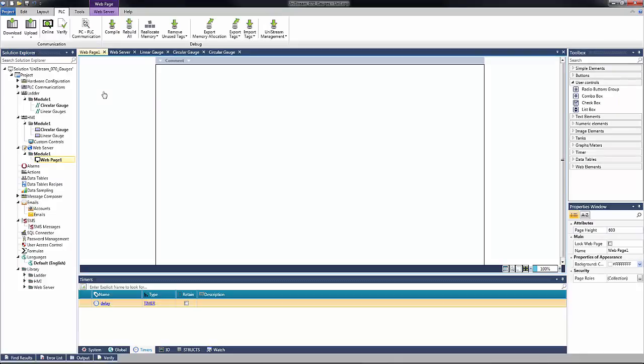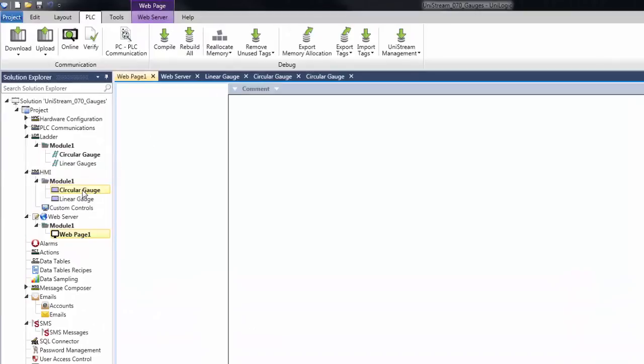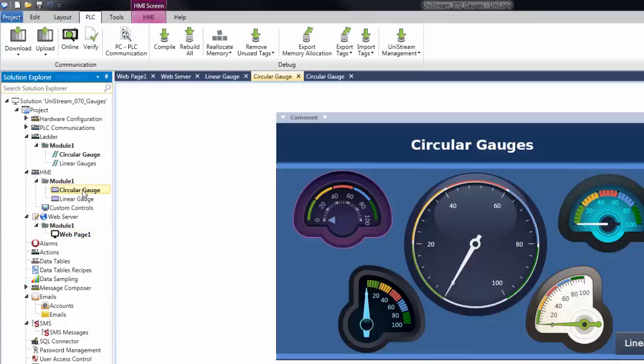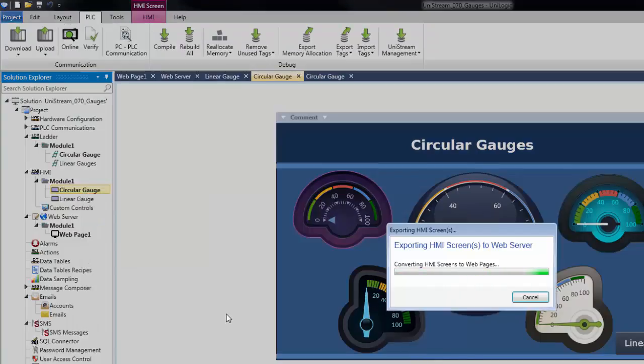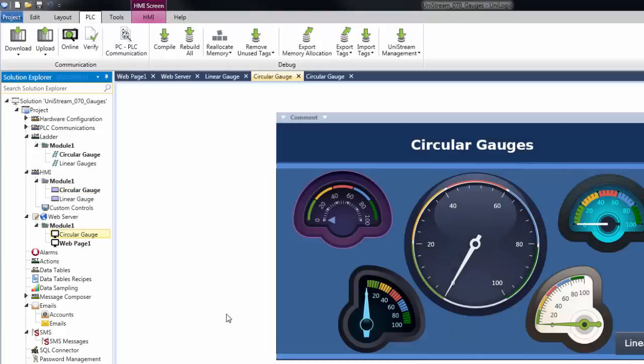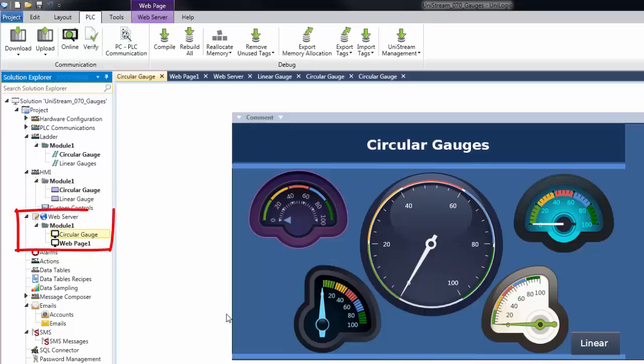To convert an HMI page to a web server page, simply select the HMI display, right click, and navigate to Export Screen to Web Server. The user will have the option to select which module in the web server. Currently one module exists; I will choose this module. The conversion is very quick, and we see the circular gauges HMI display is now available under Module 1 in the web server.